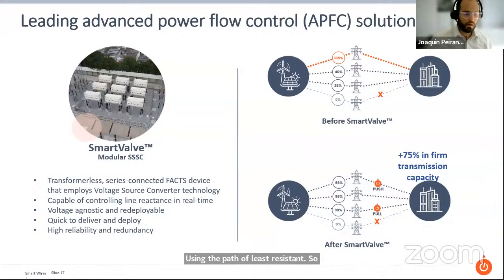Power flow control is a piece of hardware you can use to change that, by changing the reactance of the lines in real time. You can either push or pull power, meaning you create the effect of an inductor or a capacitor. At Smart Wires, we do this through power electronics—that's why it's called advanced power flow control, because it uses voltage source converter technology, similar to other FACTS devices like STATCOM. It injects a voltage in series with the line, creating the effect of a reactance that can be either capacitive or inductive.